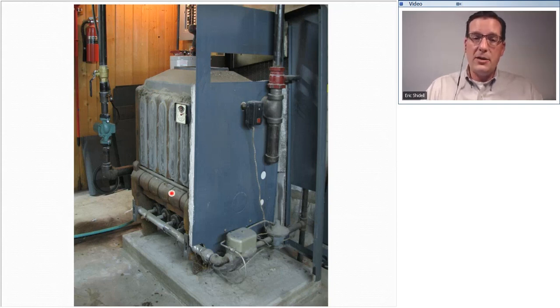But where these section seals are, there is a type of putty applied there, also around here. And by this age, that putty has largely dried out and flaked away and fallen down. As a result, products of combustion have the ability to leak out. And when you're checking one of these boilers, it's very crucial that you're checking for carbon monoxide. And check in every penetration, like where this control penetrates through the jacket and into the boiler section, where this pipe penetrates through the jacket, look for any signs of combustible or combustion products there. Look for carbon monoxide. If you're having a combustion analyzer, look for carbon dioxide. That is an indicator that your heat exchanger is leaking because these seals have failed. That's a really good time to think about a new boiler.